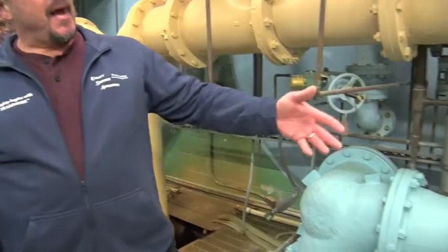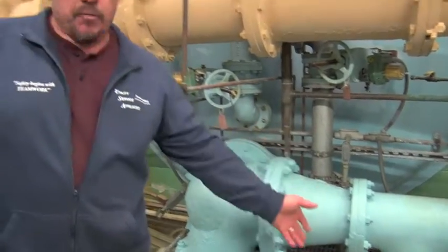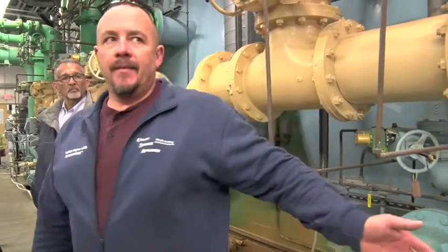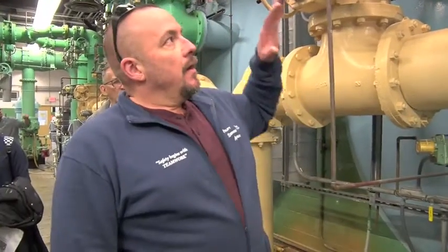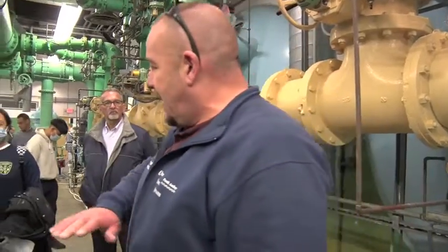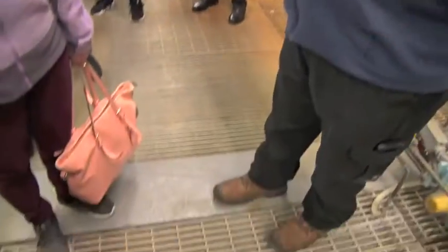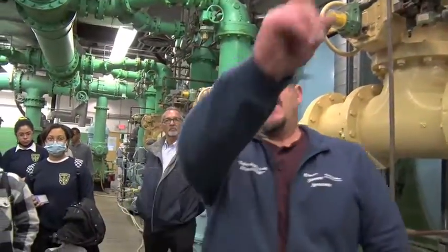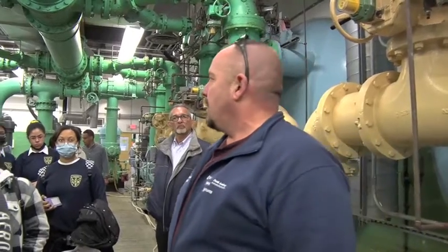Once the filter goes back in service, there's what's called a return to waste. The influent valves open up and we run the water for about 3 minutes to reduce the turbidity before we put it into the system. And actually you're standing on top of the whole header. All 8 of these filters go into one main header pipe and leave the plant here, where right outside the door we add the sodium hypochlorite for post-chlorination.